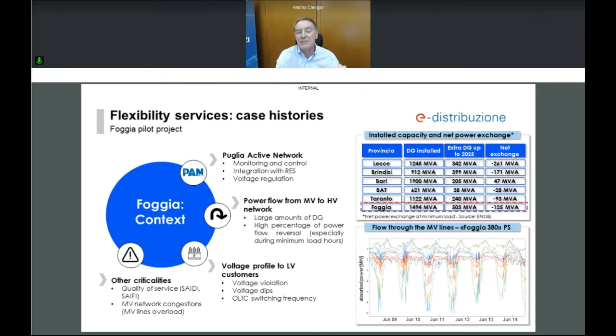The power inversion was evaluated for each single MV line. Furthermore, the power profiles, active and reactive, together with the amplitude of the currents, were also used to estimate the degree of use of the conductors in normal operation, but also and above all when the line is used as a backup feeder, so as to highlight possible limitations on the ability to reconfigure the network after failures.